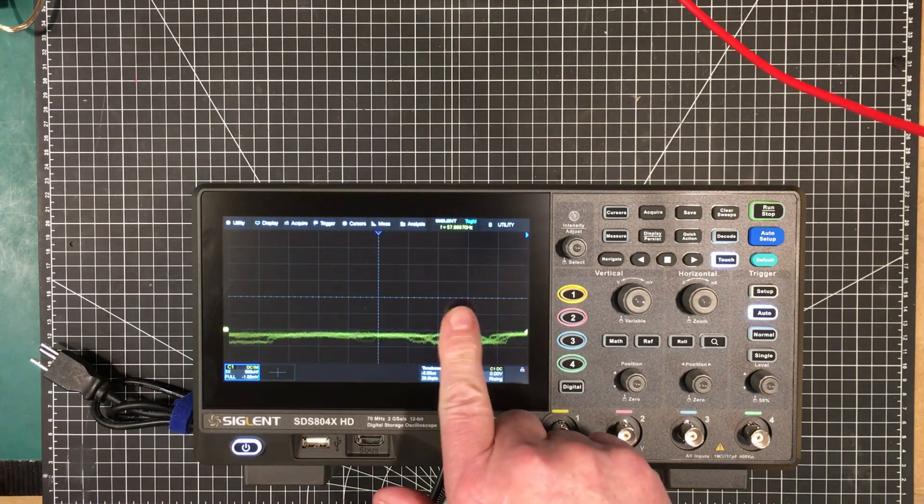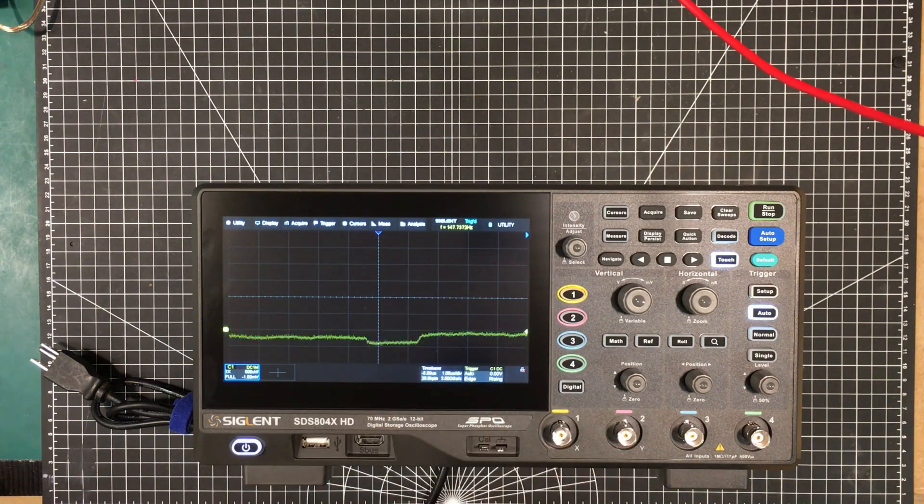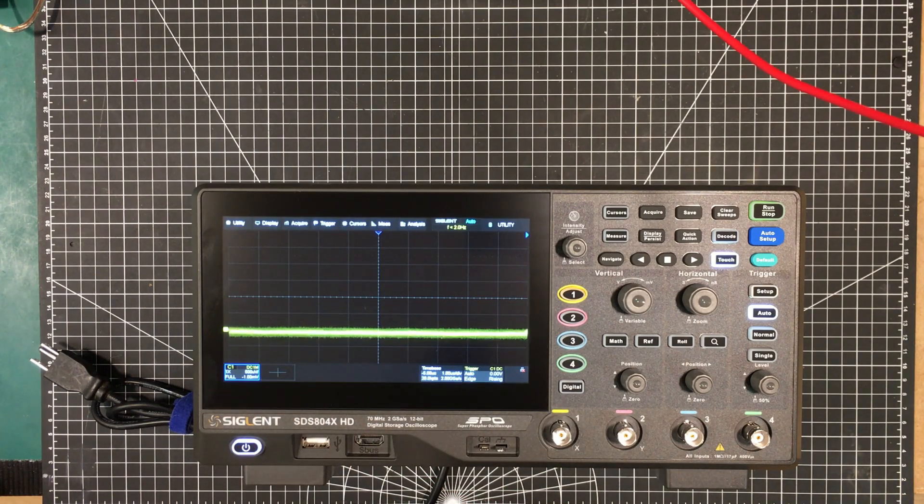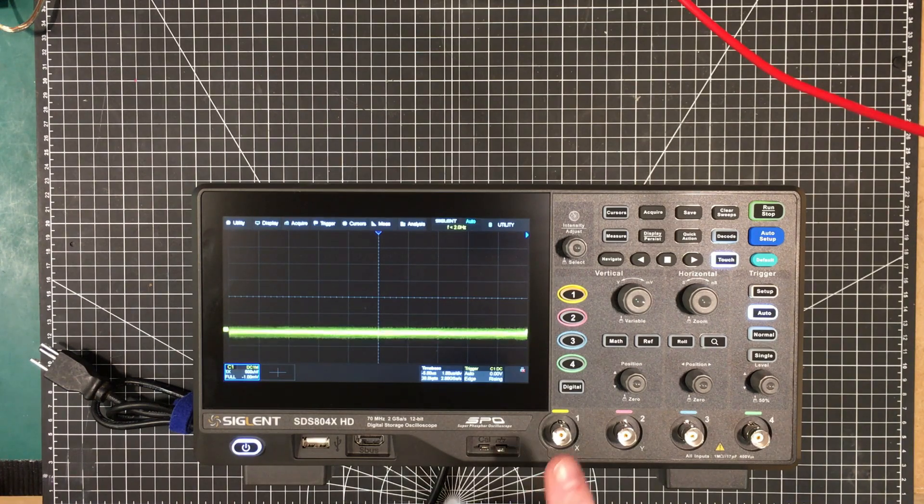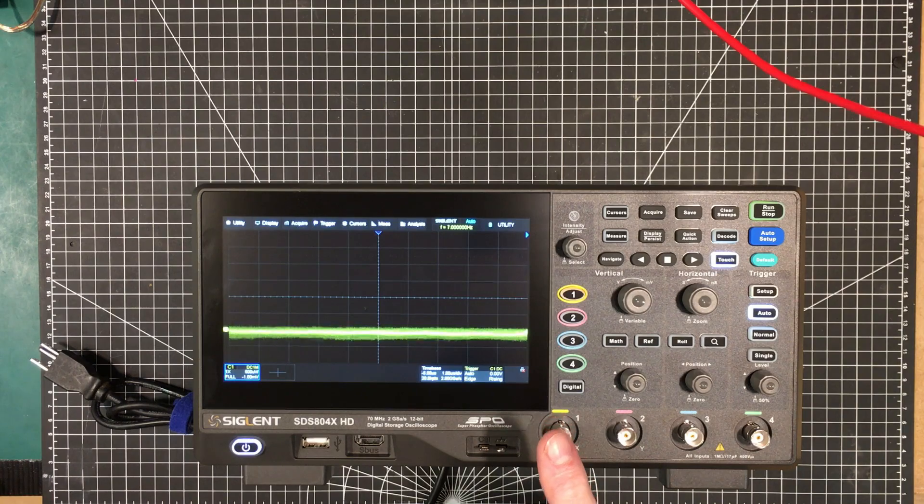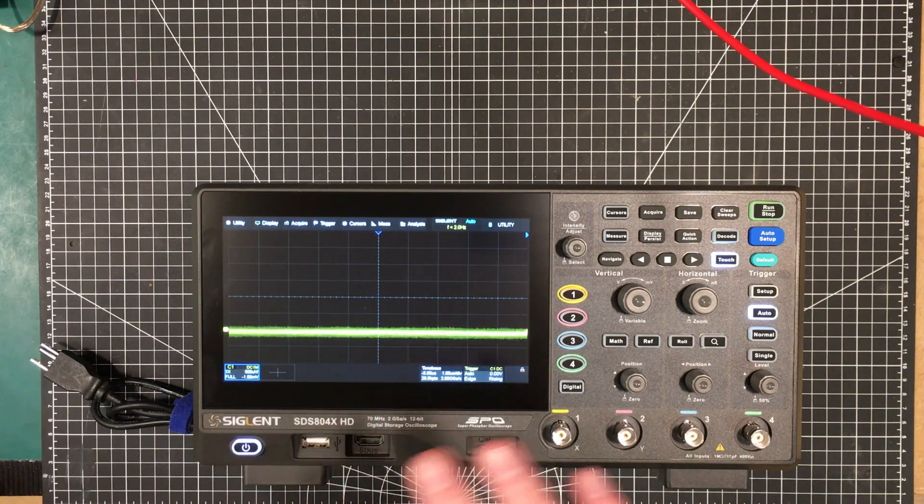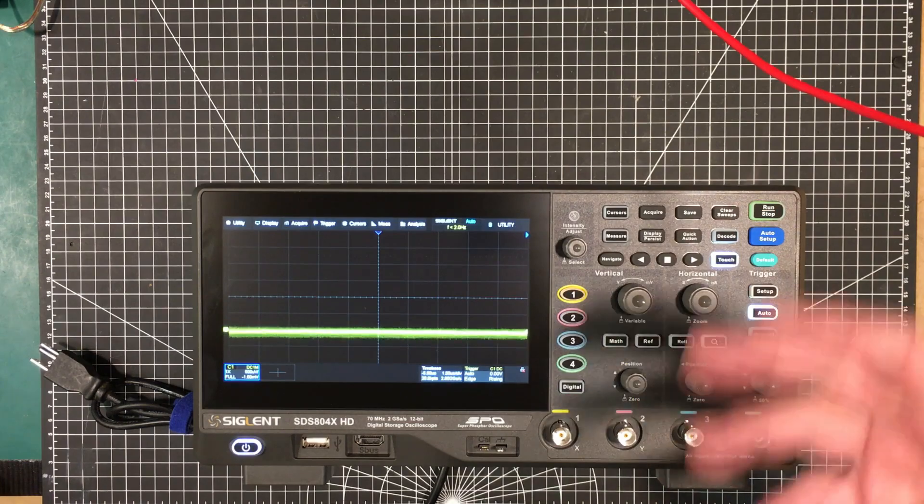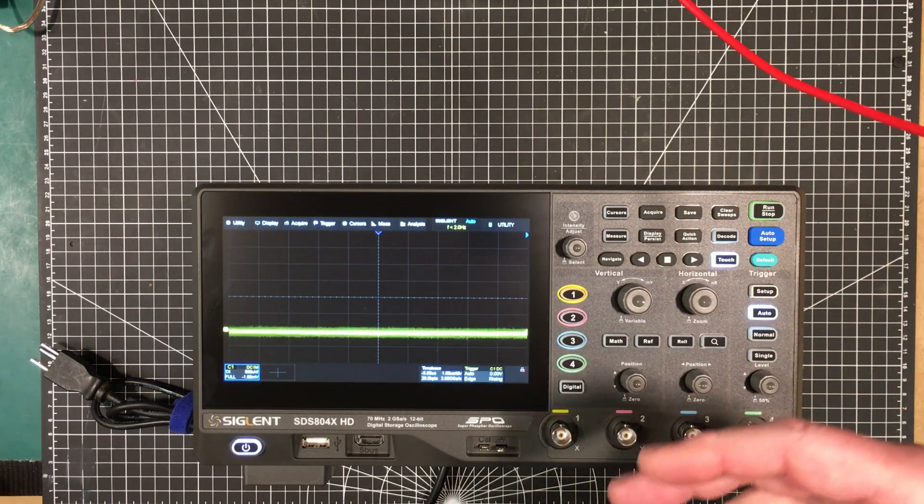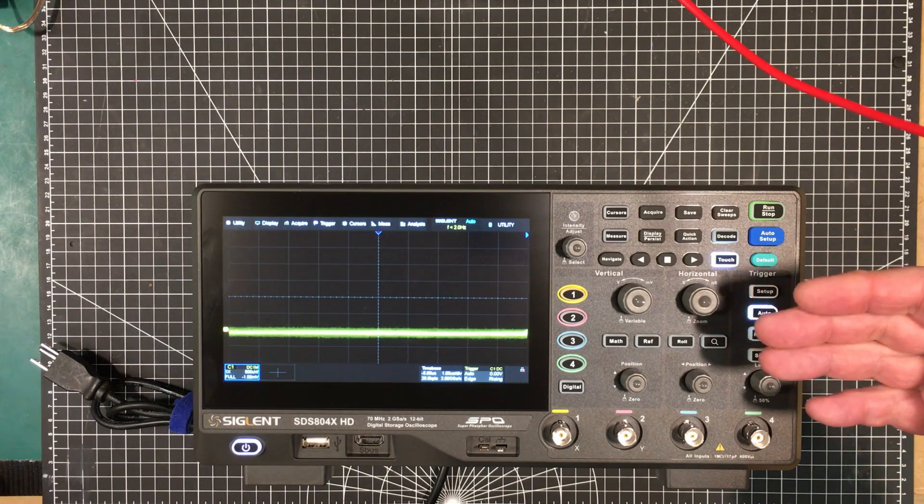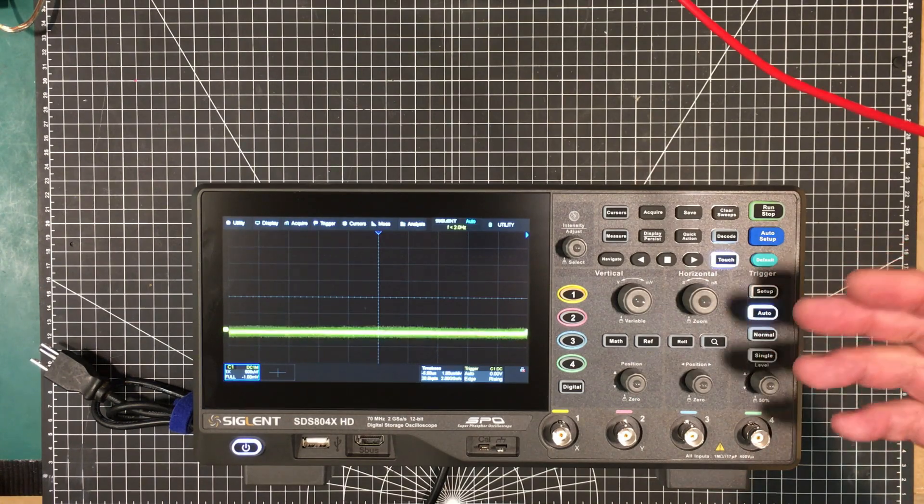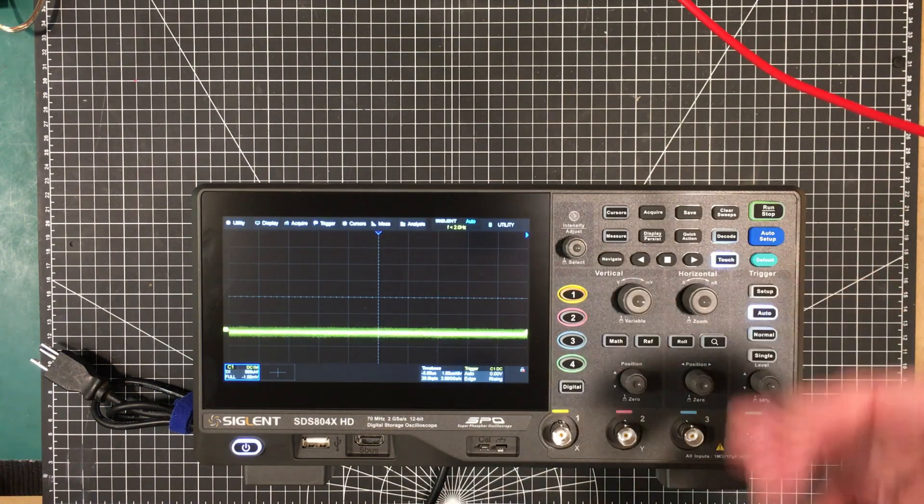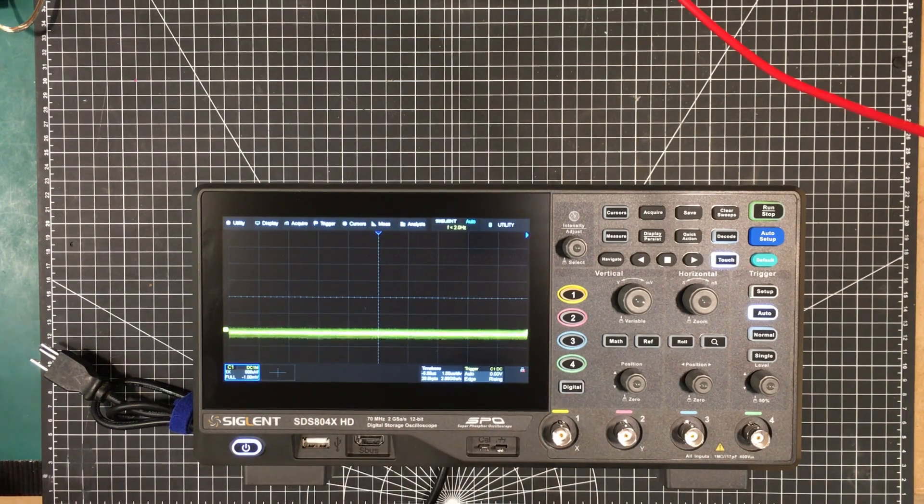Okay, that seems to have worked very well. It's taken out all the offset. Even at this range of 500 microvolts per division. So it's so sensitive. Look, just bringing my finger near that is incredible. That took 20 minutes. So if you're going to do a calibration, and I would suggest you do it once in a while, especially if you upgrade the firmware. And you know, if the machine has been off for a long period of time, it's been sitting there for, you know, you went on vacation and came back, I would run the calibration.